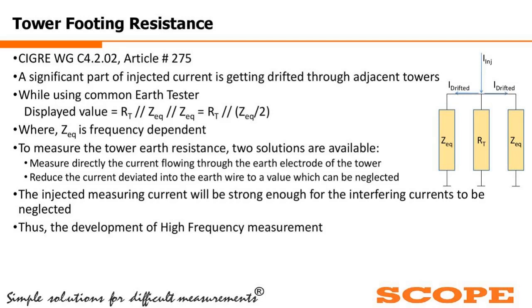Now this Z equivalent is not only pure resistance, it is impedance. The moment we talk about impedance, resistance and inductance come into the picture, and as we all know, these values are generally frequency dependent, because capacitance and inductance values vary with respect to frequency. So what is the test frequency? Based on that, the Z value changes.